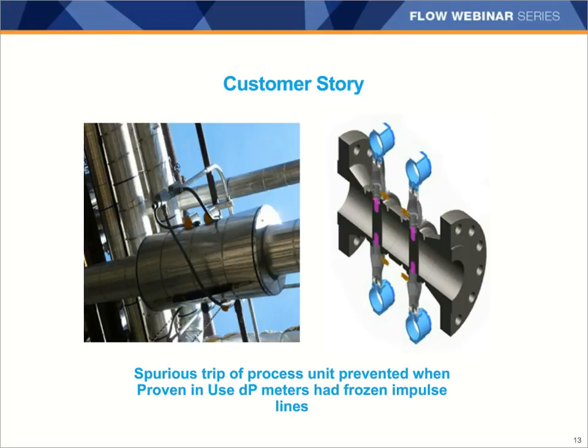However, at the time, the vortex meters didn't have IEC 61508 certification, so they ended up installing the quad vortex to get some operational data so that they could provide documentation to later use the devices as IEC 61511 proven in use. But they also installed some traditional DP meters downstream of the vortex meters, and this was to provide redundancy and to make sure that they complied with SIS until sufficient testing and usage documentation could be created for them to just solely use the quad vortex.